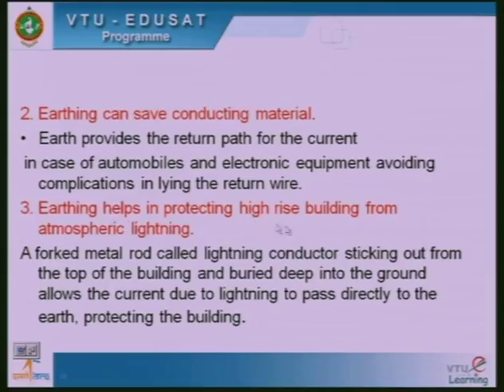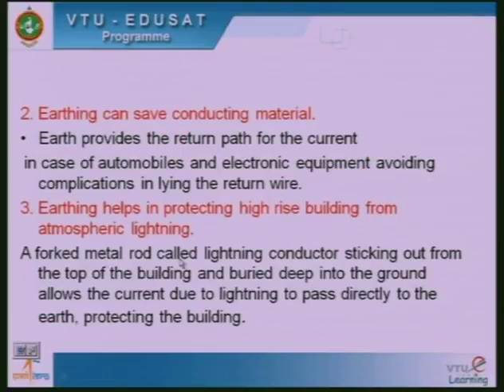Earthing helps in protecting high-rise buildings from atmospheric lightning. You might have seen at the top of high-rise buildings one forked metal rod projected out. That rod is normally called a lightning arrestor. Any natural lightning striking that conductor is provided a path to the ground through a low resistance path. So the current passes directly to the earth and protects the building. That is what we call a lightning arrestor.